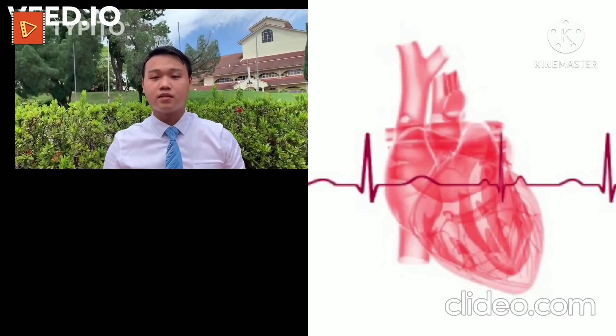Do you ever wonder how EMI occurs? EMI occurs when electromagnetic waves emitted by one electronic source or device impede the normal function of another electronic device as a result of conducted or radiated electromagnetic energy. EMI signals can affect cardiac devices because they overlap the cardiac signal range. They can interfere with the optimal function of the pacemaker in several ways. EMI will stop the pacemaker from delivering the stimulating pulses that regulate the heart's rhythm. This is because the pacemaker withholds pacing pulses if electrical potentials induced by EMI are detected within the heart rate range.